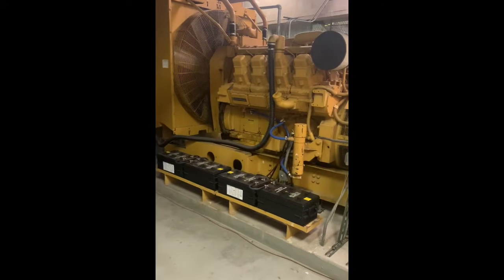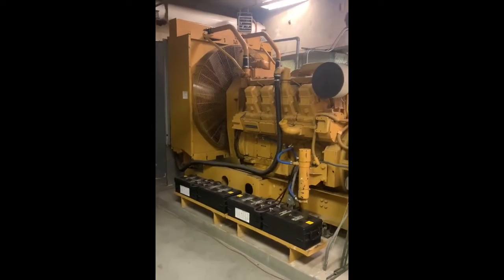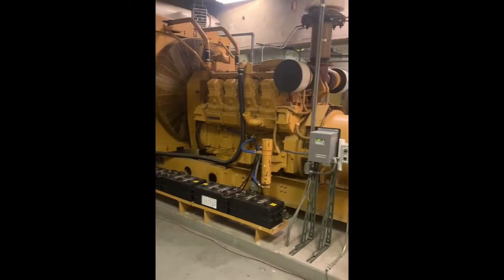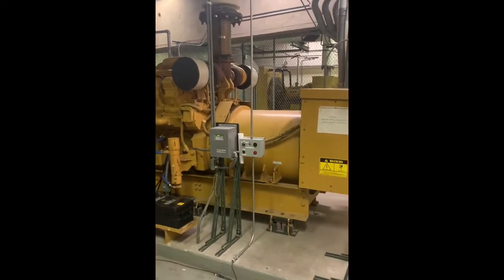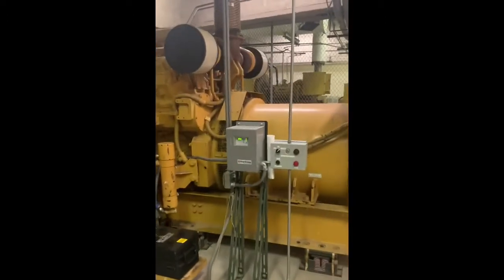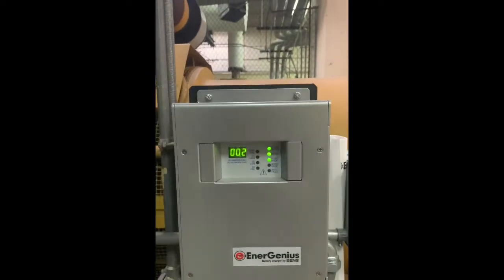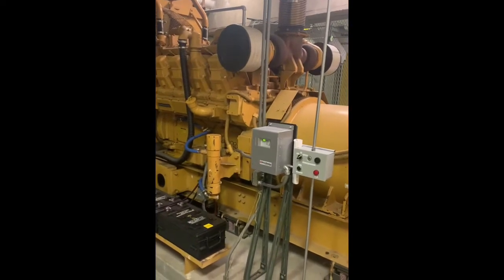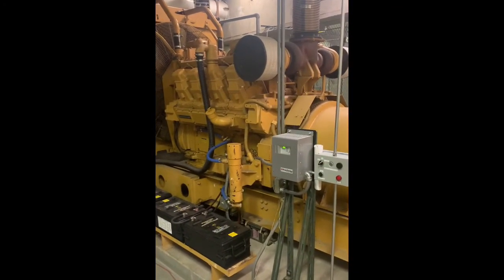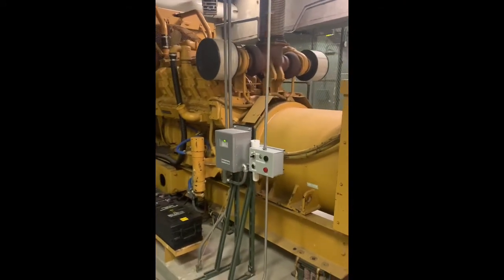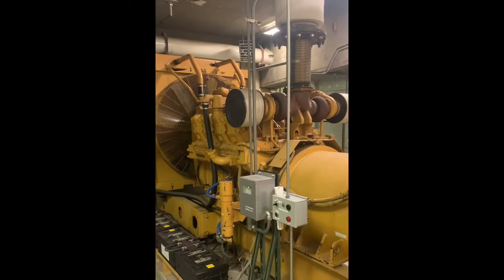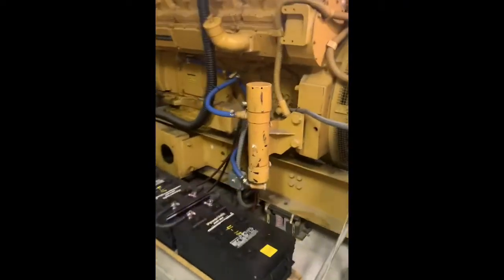Let's just talk about general maintenance. Typically we want to come in here once a shift, do a visual inspection, check for leaks, check the battery levels. Here's the information for the battery. We've got leak detection going around the entire base and perimeter of the generator, which would sound out remotely should there be a leak of fuel or coolant. So we want to check coolant levels, oil levels, air filters, water heater. This is the water heater here.